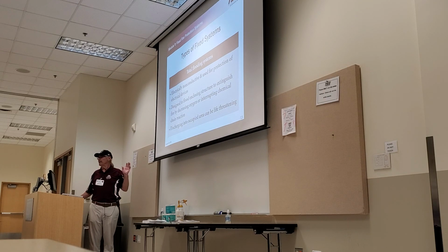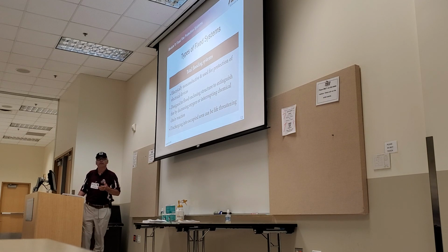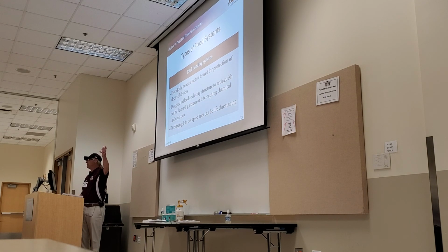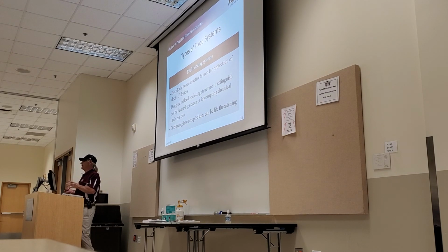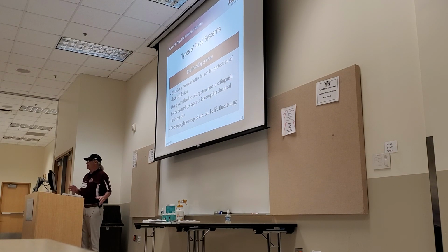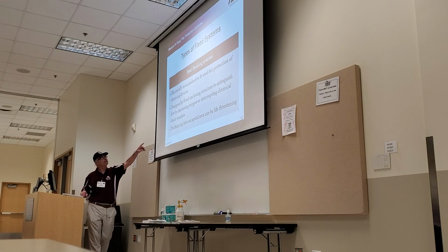But the ones that get around that, back in the days of the computer rooms, was halon 1301. I put a lot of those in. It's got the same setup, the detectors in the ceiling, the nozzles in the ceiling, but at about 5 to 6%, you could stay in the room and it would have the opposite effect, like breathing helium from balloons. Your voice gets real low. It's like a very light voice in there. It's cold too. The room gets automatically cold. But that's a chain breaking reaction.